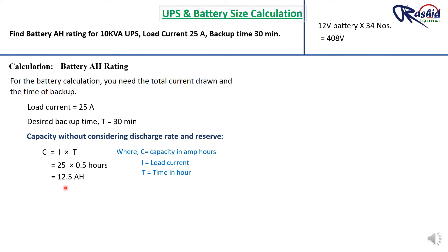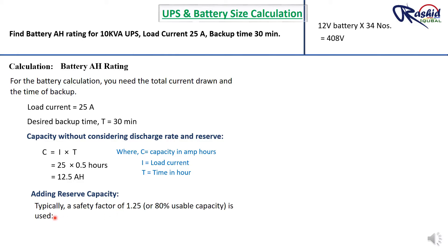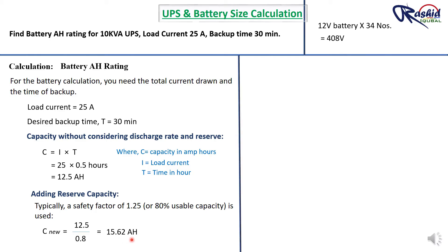This calculation does not yet consider reserve capacity or discharge rate. Adding reserve capacity: we typically consider 80% usable capacity. So C_new = 12.5 AH ÷ 0.8 = 15.62 AH. Reserve capacity refers to how long the UPS can continue to power connected devices during an outage before the battery is depleted.